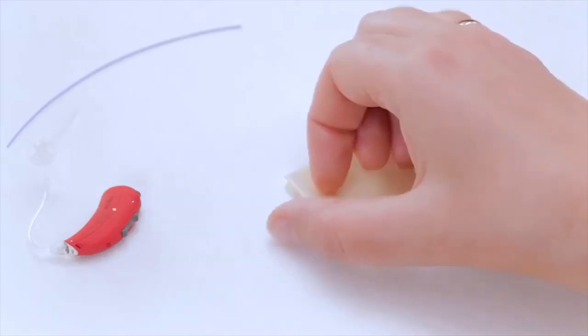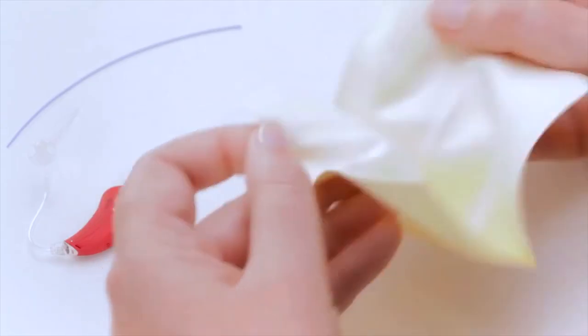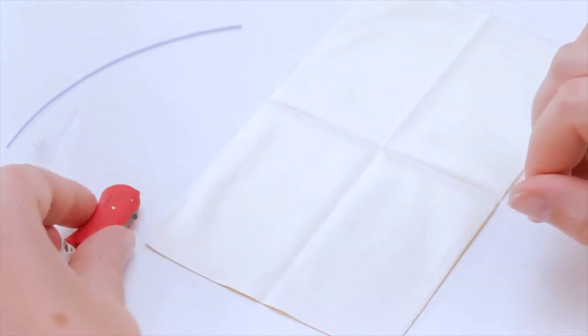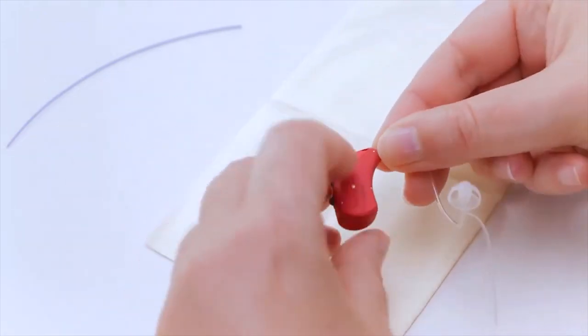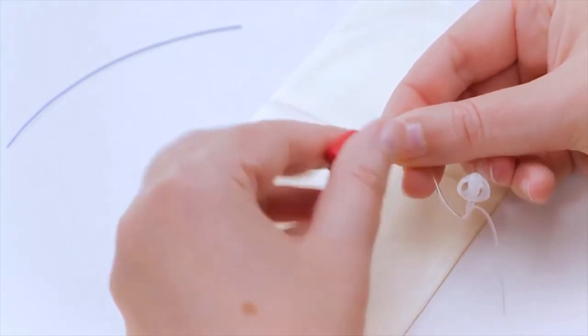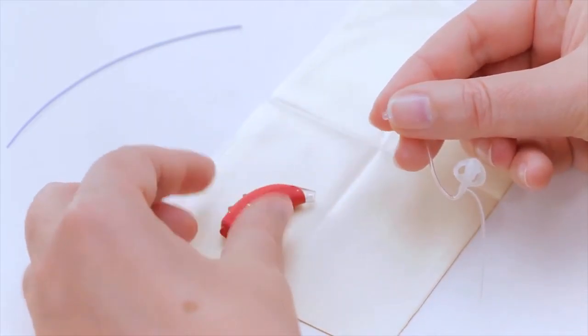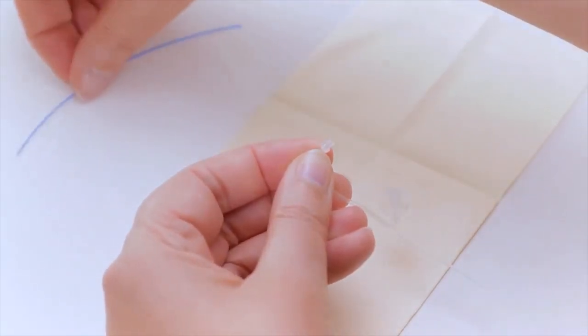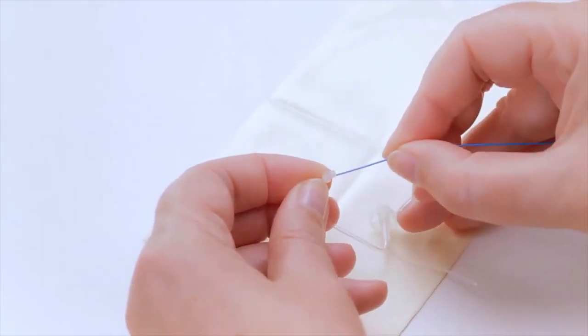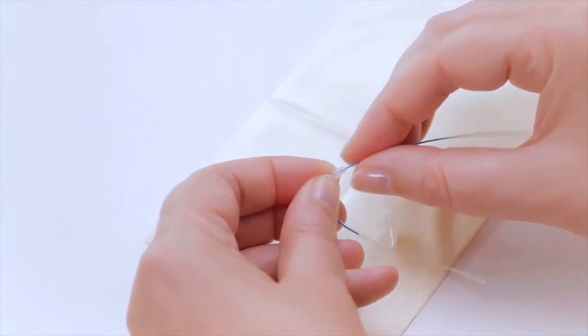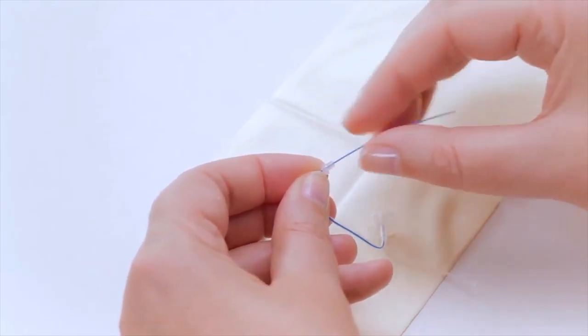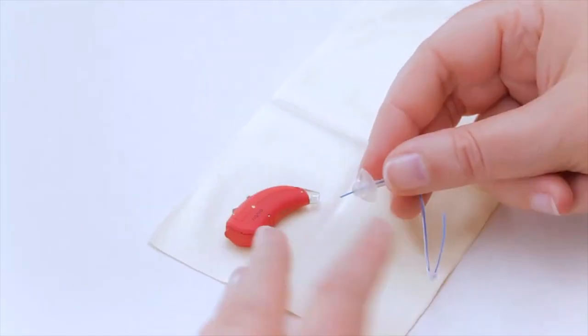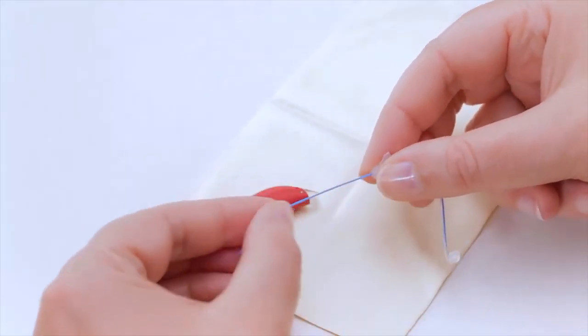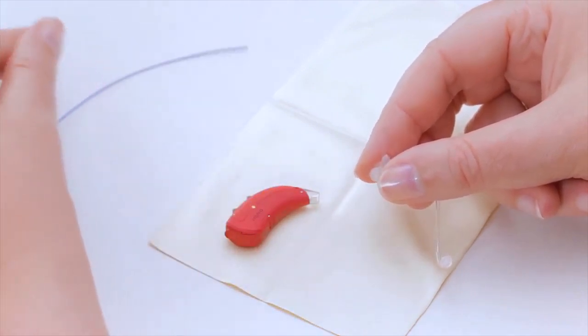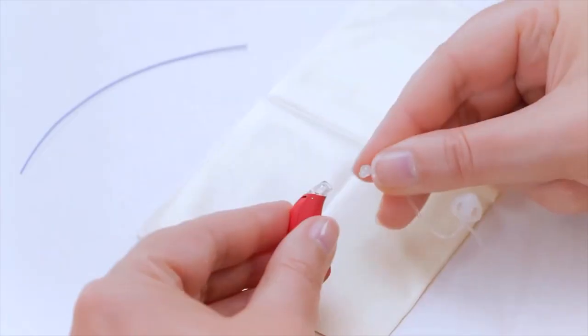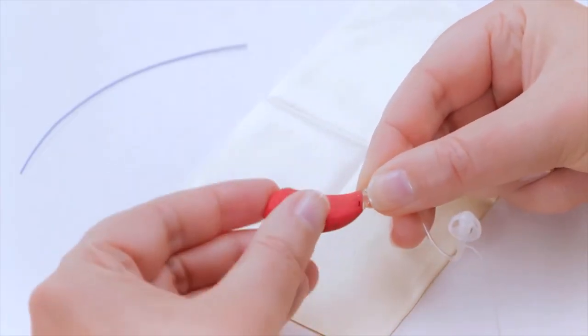Now, if you have a BTE hearing aid where the receiver is contained within the hearing aid shell, the thin tubing between the hearing aid shell and dome may become plugged with debris. In order to clean the tubing, first unscrew the tubing from the hearing aid shell. Next, thread a cleaning wire through the base of the tubing. Push the wire all the way through the tubing and out the tip. This maneuver will push out any debris or earwax from the tubing, thereby removing any blockages. Repeat this process until the tubing is clear. The tubing can then be screwed back into the hearing aid shell.